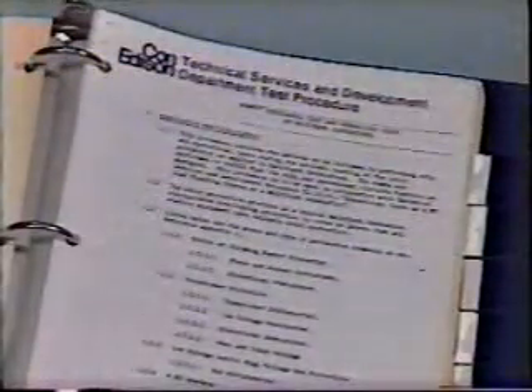To perform tests on carrier equipment, special electronic test gear is required. We'll be talking about this subject in detail in videotape PSP-13, which is entitled Power Line Carrier. With such a wide range of equipment and a large number of items to be tested, a checklist should be prepared during the planning stage. This will indicate the sequence of tests and the prescribed method. The precise methods for testing and commissioning equipment vary quite widely from company to company. Make sure you're familiar with your own company's procedures.